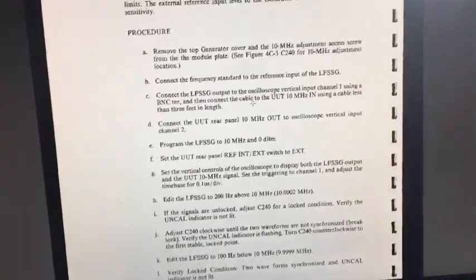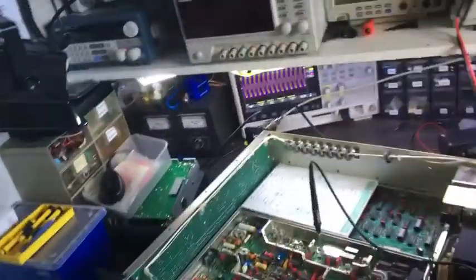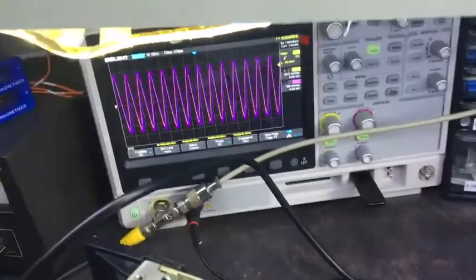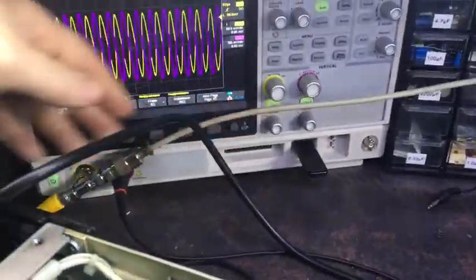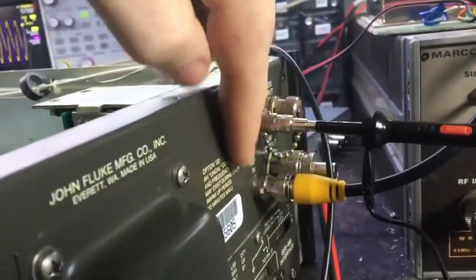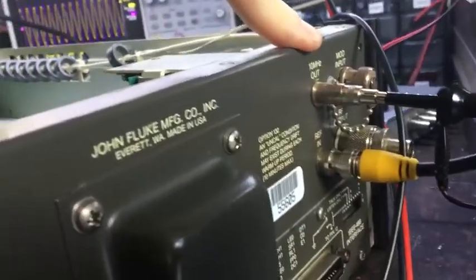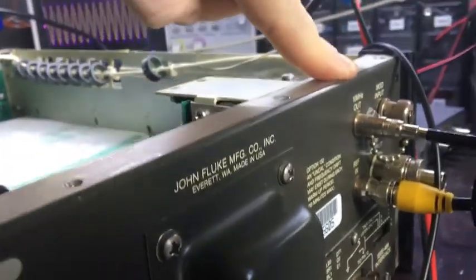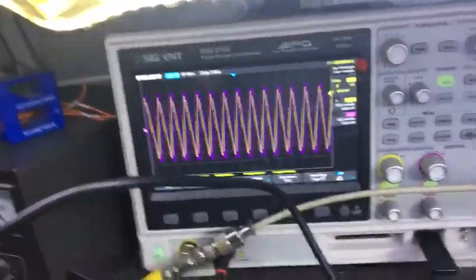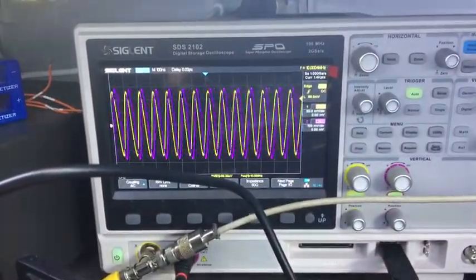I'll show you what I mean on the scope. Give me a second. Right, so I've got some dodgy leads. The grey lead is from my signal generator. This lead here is going around the back to the reference input. So the signal generator is providing reference for this. That's set for external reference. The 10 megahertz output is fed back into channel 2 as per the service manual.